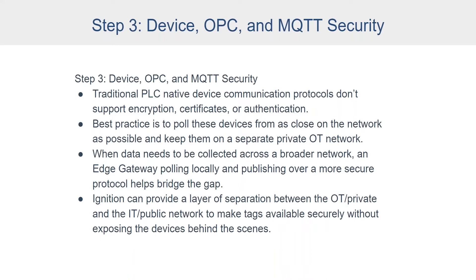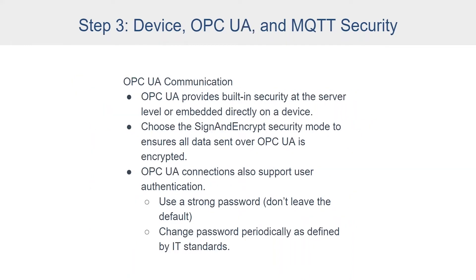Direct connections from Ignition to OPC UA and MQTT devices are generally the most easily secured connections, but we can still secure other connections as well. Talking about OPC UA and MQTT, let's go into those a little bit. OPC UA provides built-in security at the server level and also embedded directly on a device. When you connect, you can choose the sign and encrypt security mode to ensure that all data sent over OPC UA will be encrypted.